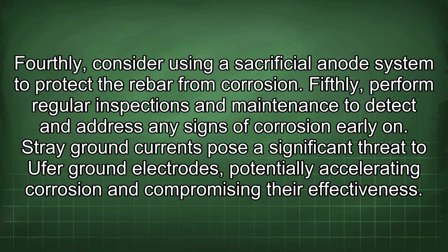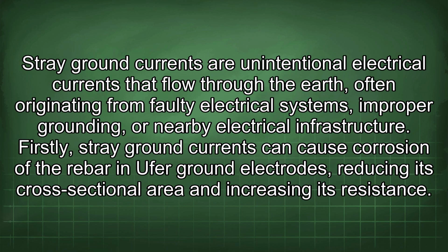Stray ground currents pose a significant threat to Ufer ground electrodes, potentially accelerating corrosion and compromising their effectiveness. Stray ground currents are unintentional electrical currents that flow through the earth, often originating from faulty electrical systems, improper grounding, or nearby electrical infrastructure. Firstly, stray ground currents can cause corrosion of the rebar in Ufer ground electrodes, reducing its cross-sectional area and increasing its resistance.